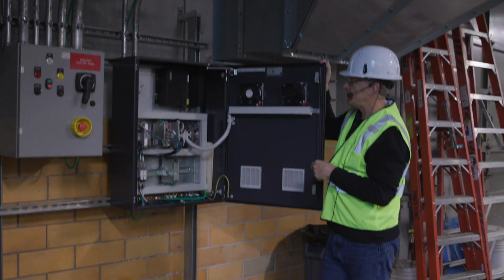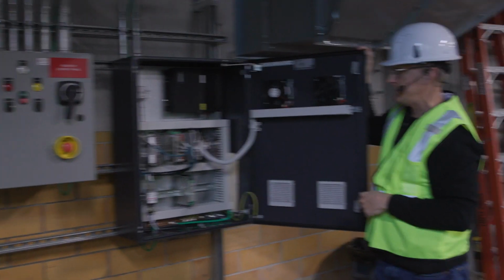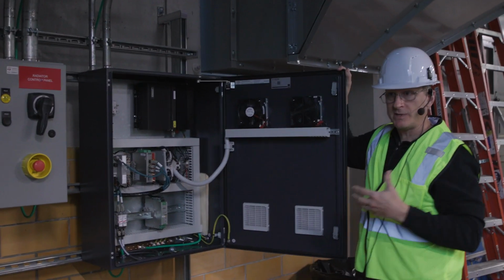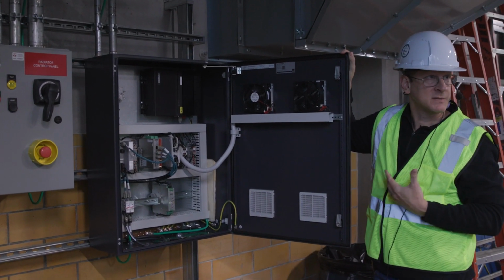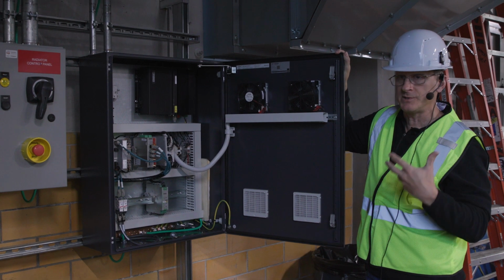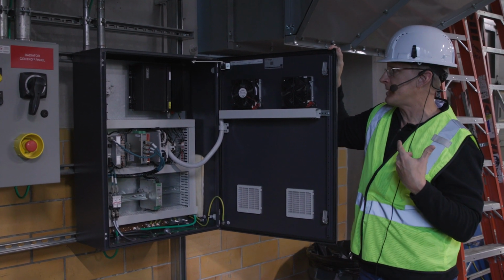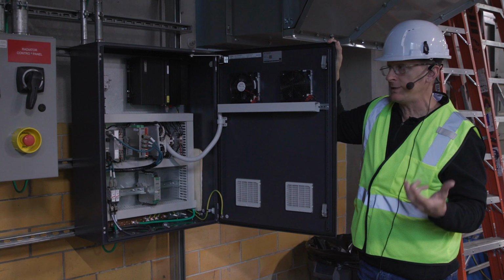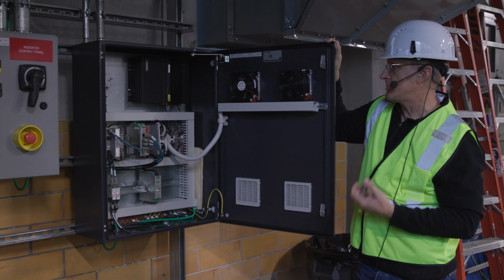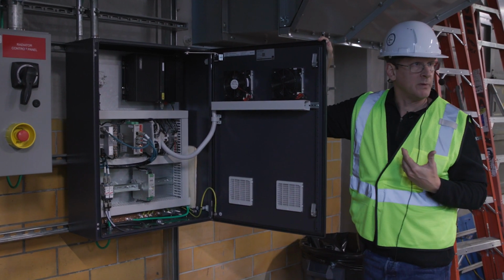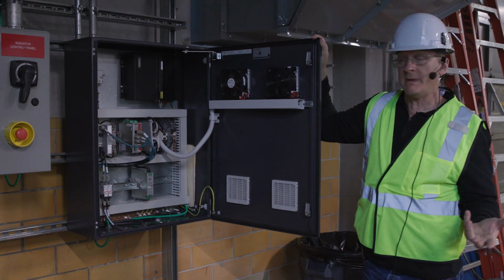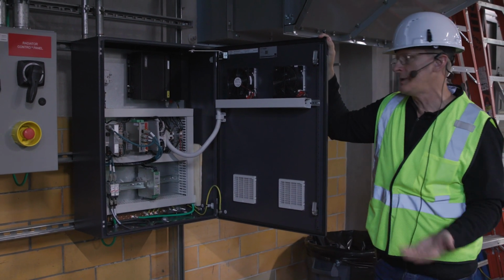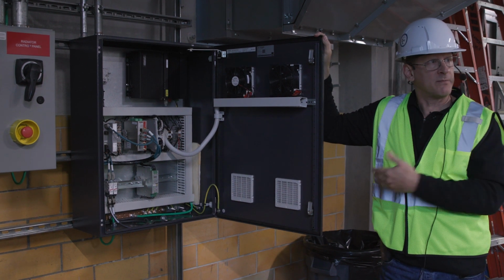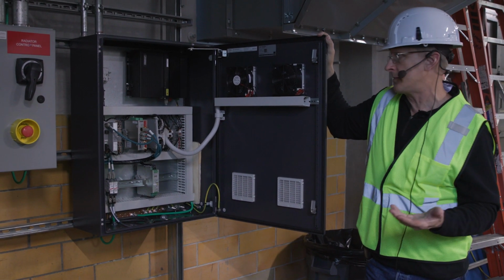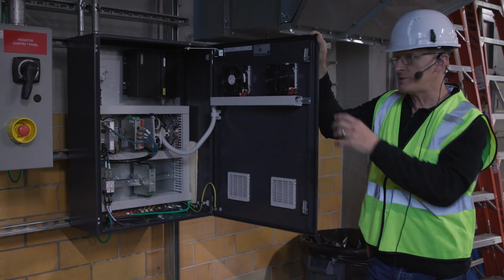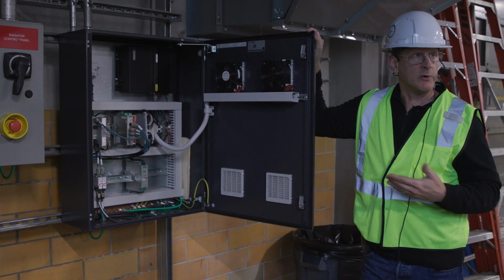So basically in this panel you have what we call our box PC. All that's doing is basically recording and storing information that it gets from the system. So it's recording logs and storing logs, snapshots of plots, storing history, so that at any time, if you need to come in for a maintenance evaluation and take a look at the log history for troubleshooting, or for whatever reason, we can go and extract information from this to see what is going on with the system.